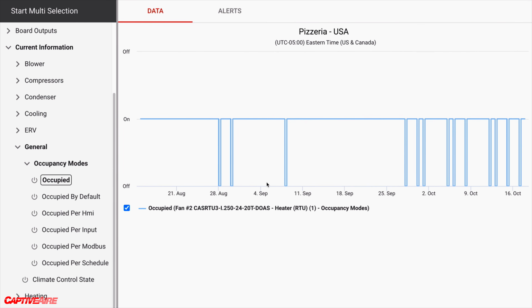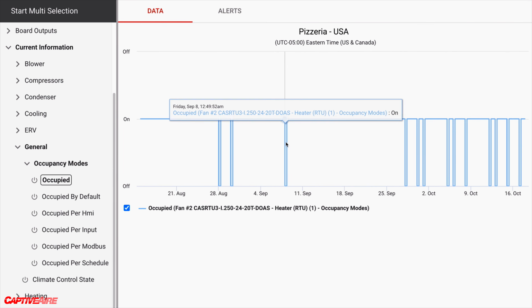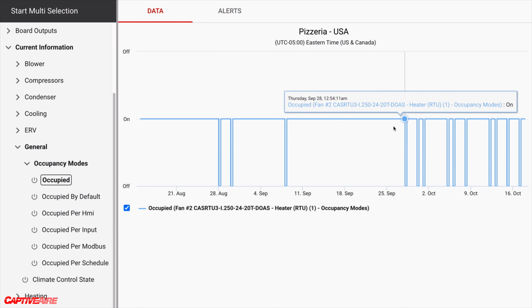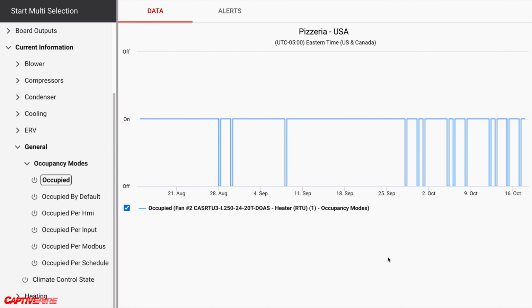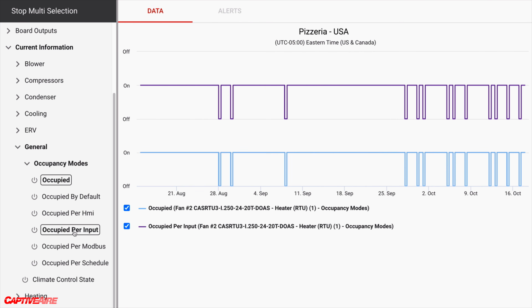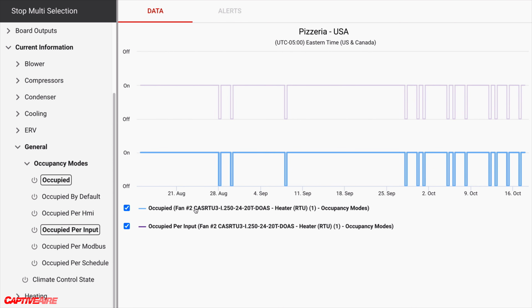All right, I can see that we've got a window here for Friday, but that goes all the way through Thursday. So we would have expected at that point to be going into unoccupied modes. Now, I'm guessing it's likely because of the interlock, but let me see. All right, so I can confirm it's going into occupied because of that interlock with the hoods. So this is certainly going to be a big piece of energy wasted.